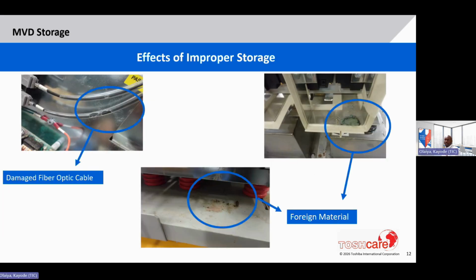So here are some examples of the effects of improper storage. You can see some damage to the fiber optic cables, foreign material getting into the modules. And what makes these types of effects dangerous is the fact that they would not necessarily show up right away. These are things that could lead to problems further down the road, which would in turn ultimately reduce the drive life or worse, cause damage.